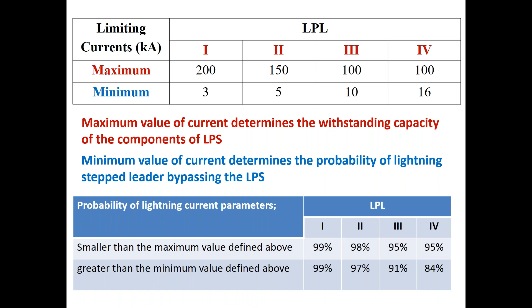So for example, if you go to level 1 protection, then the system can withstand up to 200 kiloamperes. But on the other hand, if you go for example to class 3 or level 3 protection, it can withstand only 100 kiloamperes. What does this minimum value mean? It means the minimum current of a lightning that the lightning protection system can intercept. So in other words, if the lightning current is very low, there is a probability that the lightning protection system will miss the step leader, and the step leader can get attached to an unprotected part of the building.